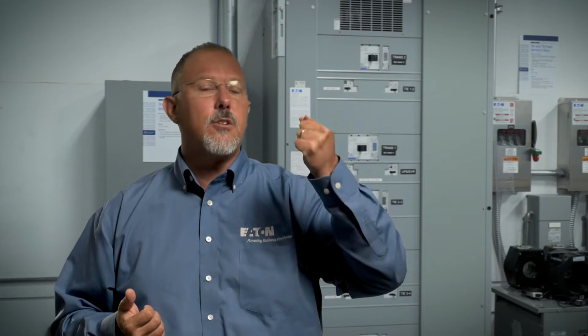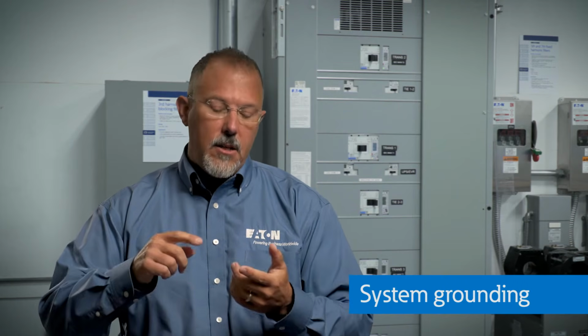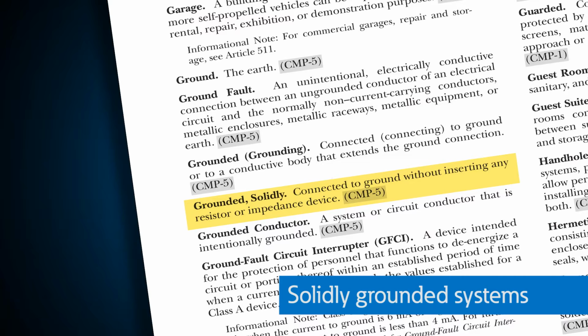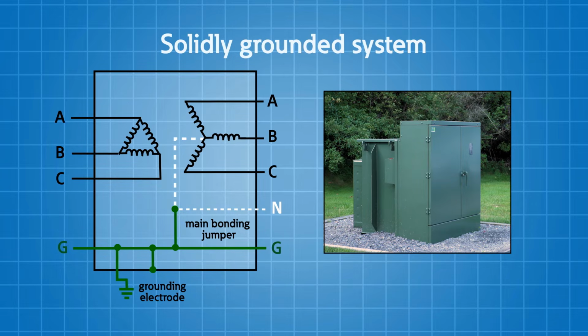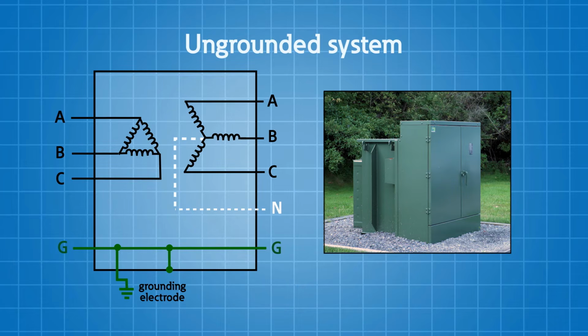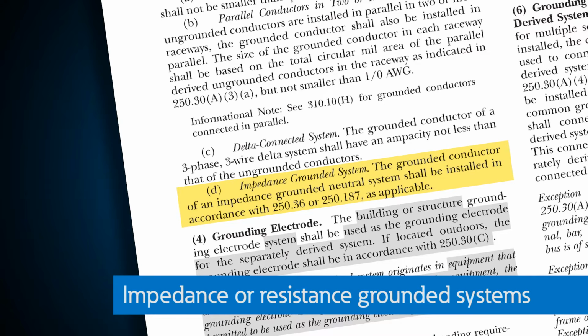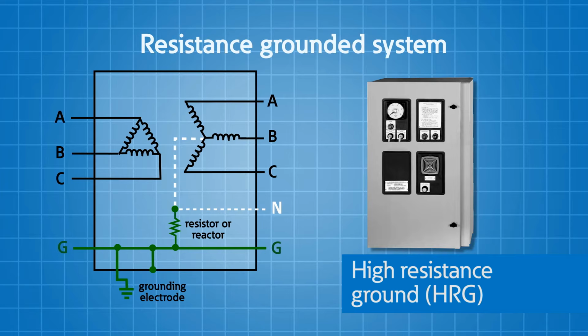All right, so everything that we've talked about so far has been about grounding and bonding of components and electrical systems. We're establishing that connection at the service or at our separately derived system between the grounded conductor and our equipment, bonding and ground and earth. Now we're going to talk about system grounding, and we're going to hit solidly grounded systems versus resistance or impedance grounded systems. Solidly grounded, when we use that type of terminology, we have a solid connection to the earth at some point in the power distribution system. There's no resistor or impedance inserted in that connection point. Ungrounded systems are just that. There's no connection to ground or a conductive body that extends that ground connection. We're insulated from ground. Your impedance or resistive grounded systems are systems that are connected to the ground, to the earth, through an impedance.